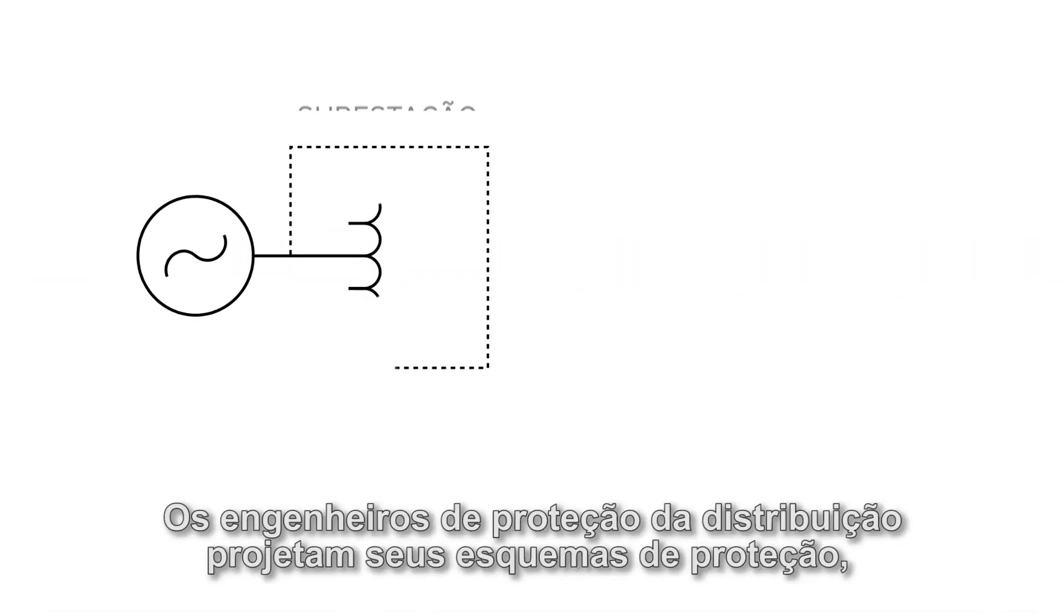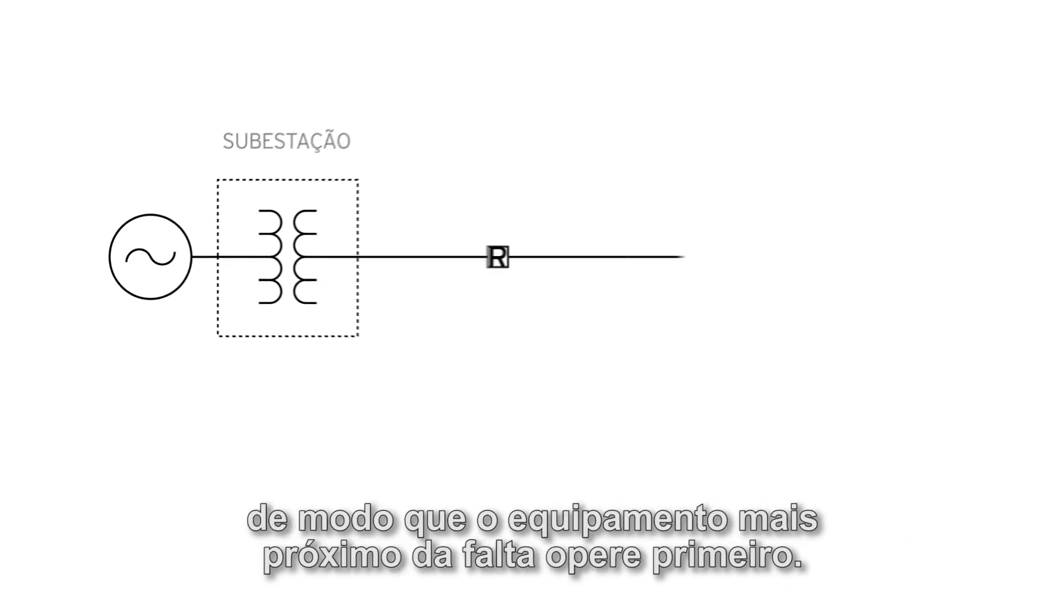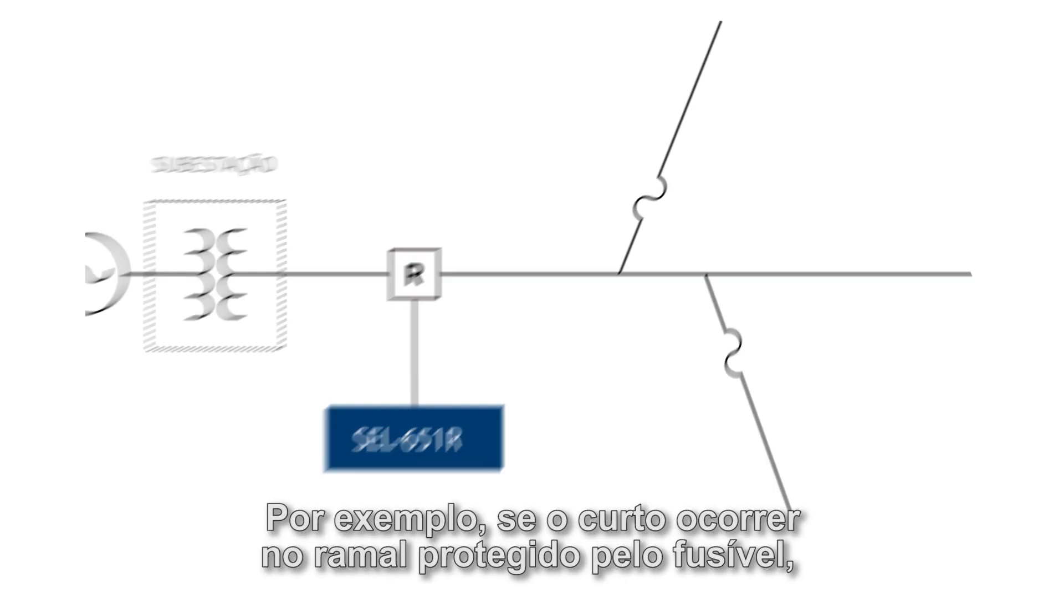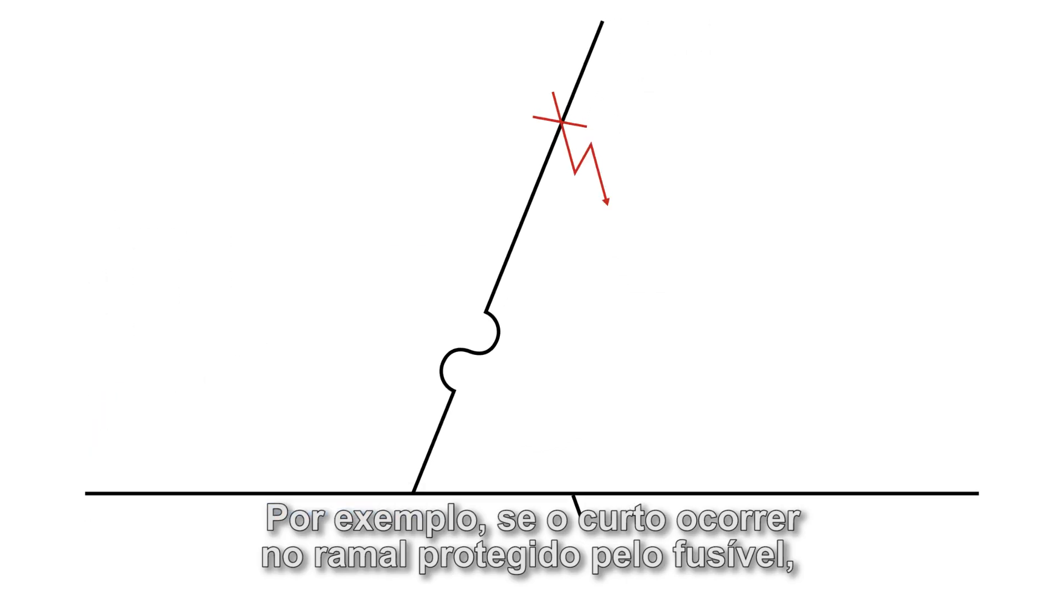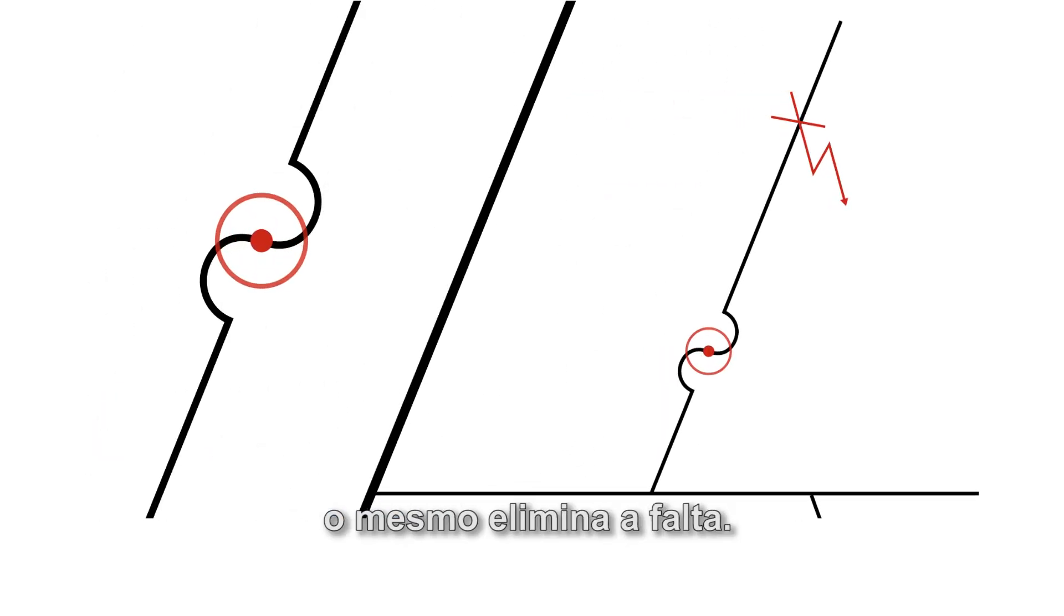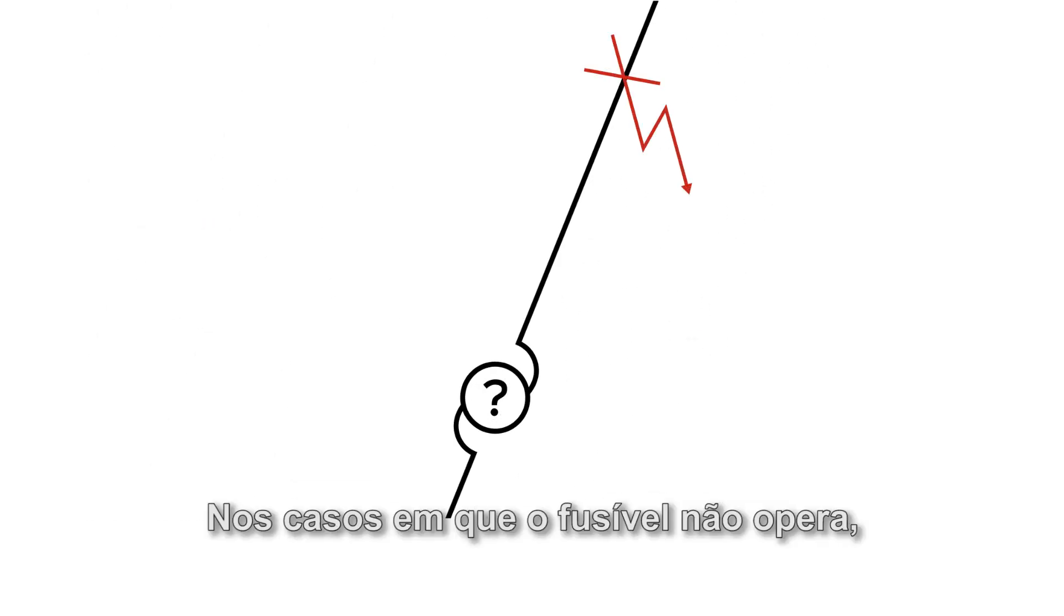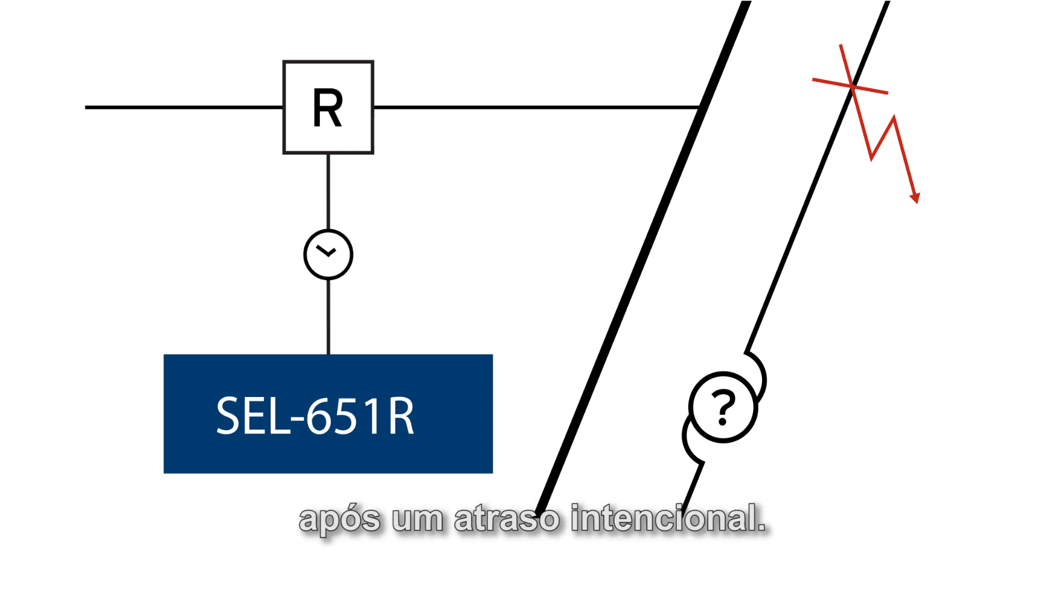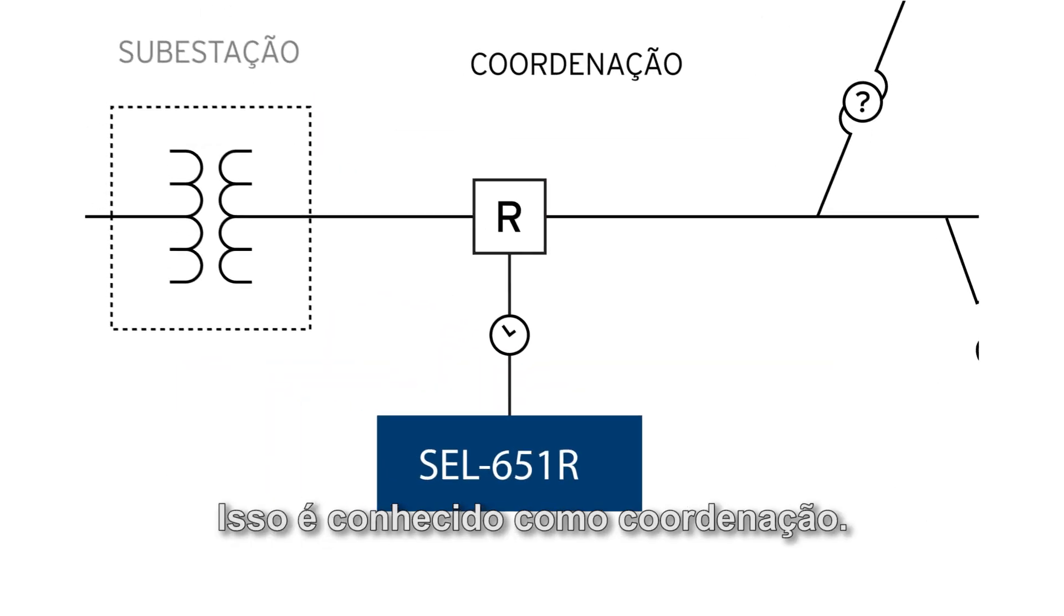Distribution protection engineers design their protection schemes such that the device that is closer to the fault operates first. For example, if the fault is on this fuse-protected tap, the fuse clears the fault. In cases where the fuse fails to operate, this fault is still cleared by the recloser and the recloser control after an intentional delay. This is known as coordination.